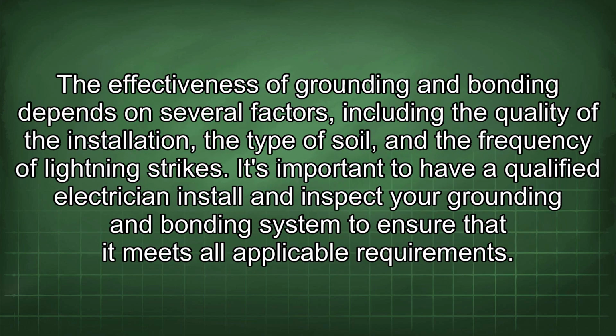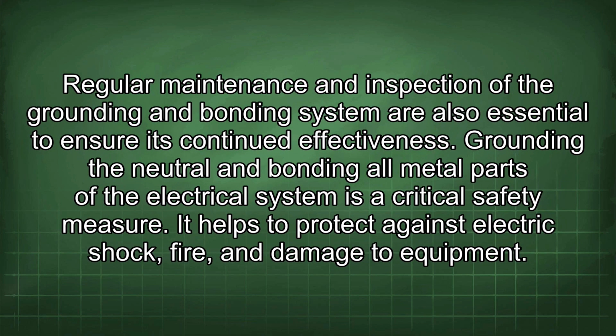The effectiveness of grounding and bonding depends on several factors, including the quality of the installation, the type of soil, and the frequency of lightning strikes. It's important to have a qualified electrician install and inspect your grounding and bonding system to ensure that it meets all applicable requirements. Regular maintenance and inspection of the grounding and bonding system are also essential to ensure its continued effectiveness. Grounding the neutral and bonding all metal parts of the electrical system is a critical safety measure.